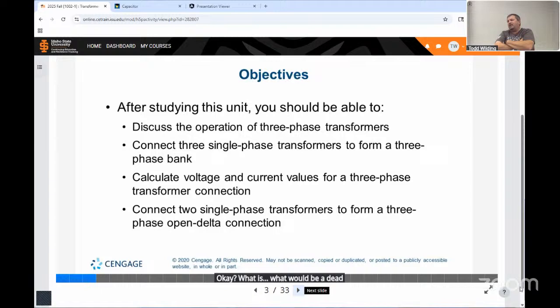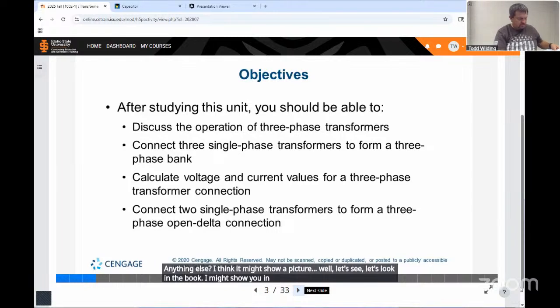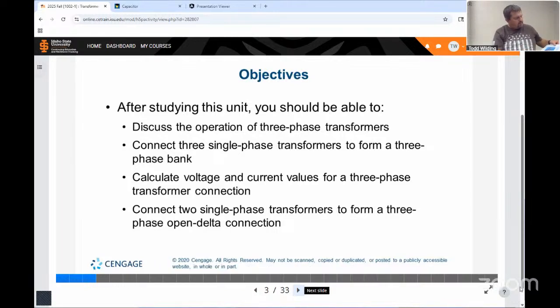What would be a dead giveaway if it's in a Y connection? Nope, you can't see that clear up on a 30-foot pole. Anything else? I think it might show a picture. Well, let's see. Let's look in the book. I might show you in the book here. So page 674. Figure 28-7. That's what I'm talking about. I got three transformer tubs sitting on top of that pole. How am I going to tell if those are connected in a Y or a delta?